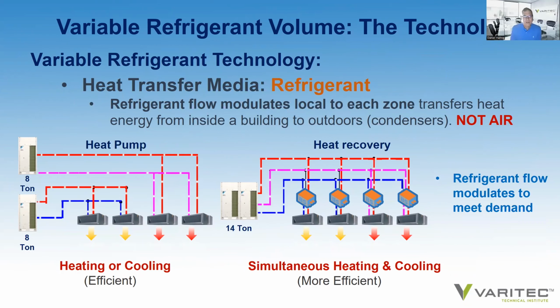And here's a graphic that illustrates the dynamic. There are two variable refrigerant technologies. There is heat pump technology, where condensers can be in either heating or cooling load, and you have to be careful on how you zone heat pump technology to make sure that you have the proper grouping of air handlers per condenser, depending on which zone in the building is getting the greatest load or seeing the greatest load. However, a little more energy efficient approach is to use heat recovery, where you can actually do simultaneous heating and cooling from common condensers. This is achieved by using a third refrigerant loop that actually deposits refrigerant to branch selector boxes that modulate refrigerant flow strategically to each zone's air handler, so it can provide either heating or cooling while modulating refrigerant flow to efficiently do so.